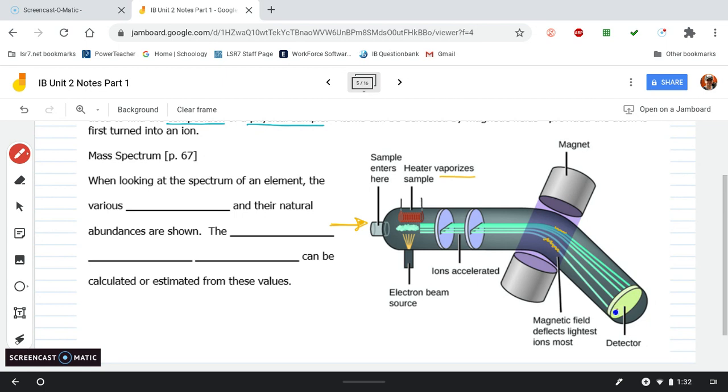They come down here and hit the detector in this spot, and then over here and over here, hitting in all these spots. The detector looks at the data, the mass values, and the types of things that are put in there, and runs it through a computer database, and it says, oh, this was these chemicals, and these chemicals are found in this paint or in this type of plastic, which is used in these tennis shoes. The device is usually hooked up to a massive database, and the database says, okay, this is what your chemical was. Anyway, we do not have one of these because they are extremely expensive, but that's how it works.